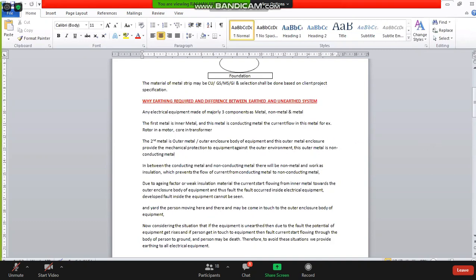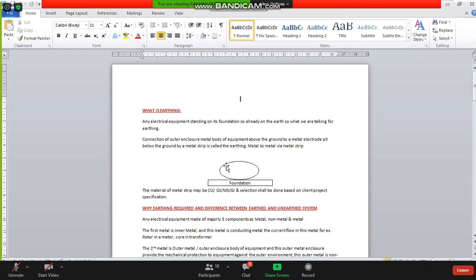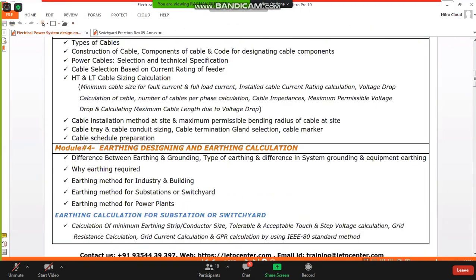So this is why we do earthing. That is the basic concept of why we do earthing, and what is earthing? The connection of the outer enclosure metal body of the equipment above the ground to a metal electrode pit below the ground via a metal strip is called earthing. The material of the metal strip may be copper, galvanized steel, mild steel, or galvanized iron, and the selection shall be based on the client project specifications. The size shall be selected based on the amount of the fault current.